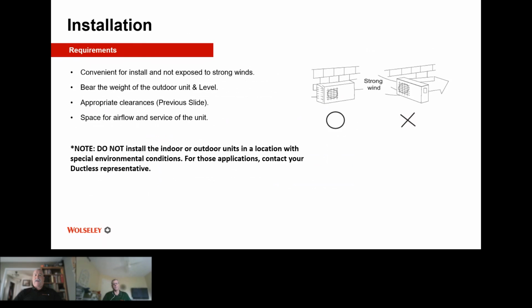We want to make sure we have the appropriate clearances from snow loads. As Joey said before, 15 to 18 inches is good. Get it on a stand, and whether you put a pad on the stand or whether you do wall brackets and you put a pad on the wall brackets, get it off the ground. We want the condensate to get away from the unit. We do not want any kind of ice buildup in these outdoor units at all. Okay? So, and just take a look at your installation manual.